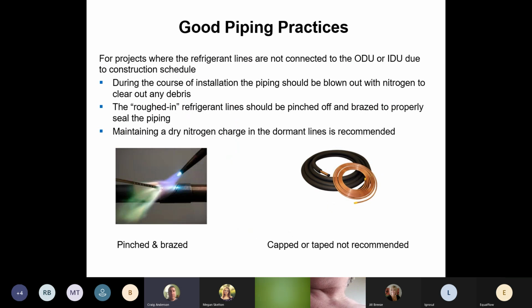Good piping practices, standard. A lot of guys do new home construction. They throw the lines in, then somebody's going to go back and put the air conditioner in. Start crimping the pipes, soldering them outside, and quit taping them, putting caps on them. I don't know how many job sites you've been to where the guys have parged it and there's cement all sticking on the outside of the copper because we taped it and it's fallen off. We have no idea what's gone in through that copper line now. We have it hooked up to our coil inside, so blowing it out is out of the question. If we blow nitrogen through it, then we don't know where we're putting that dirt.